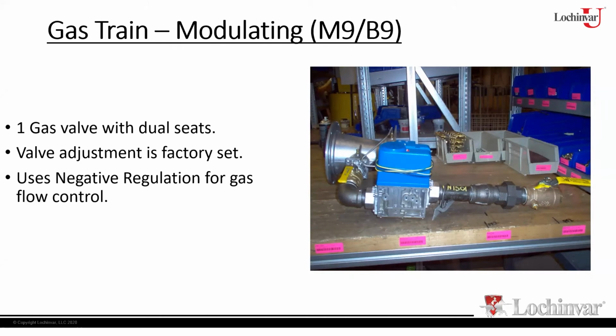Now, the valves themselves, 2 adjustments. Each valve will have a bias adjustment and a throttle adjustment. So there's always 2 adjustments on a neg-reg gas valve. Primary adjustments will be done at high fire, which will be done with your throttle. The throttle adjustment is basically just a window. All you're doing is opening a window in the valve, which allows more gas to flow through the window. So if I need to adjust to get my CO2 into range, I'm going to adjust the size of that window. If my CO2 is high, I'm going to close the window off a little bit. If the CO2 is low, I'm going to open it up a little bit. So that's what I'm doing with the throttle.